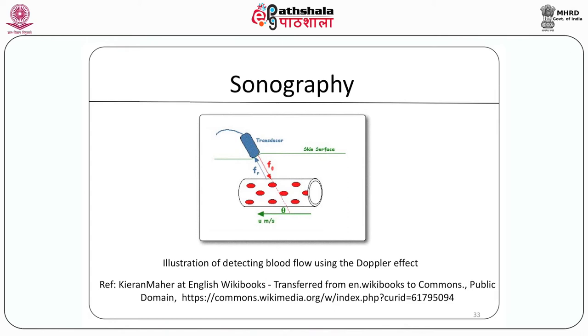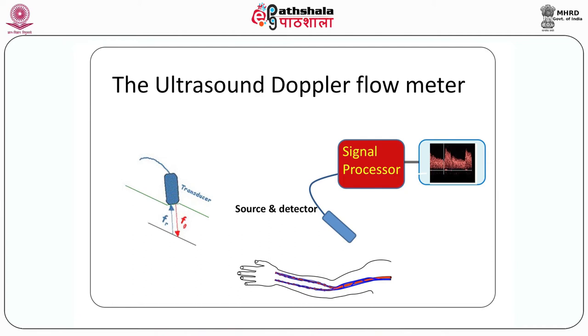The Doppler ultrasound is not only used for measurement of the absolute value of blood velocity and volume, but it also helps in visualizing the blood flow. The probe in this imaging equipment is mechanically coupled to a position resolver, which makes an electrical output. Imaging is done by moving the probe on the surface of the skin and developing a 3D image using a computer. Thus, it is possible to construct anterior, posterior, lateral, and cross-sectional scans of blood vessels. The ultrasound Doppler can also be used to measure cerebral blood flow — this is called transcranial Doppler.